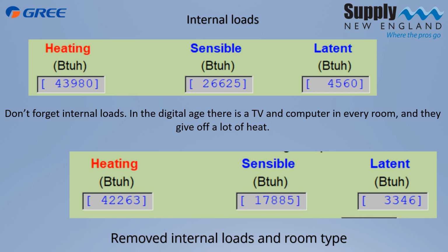By removing the internal loads, look what happened. We changed our heating BTUs. Not a lot, but some. Look what happened to our sensible though, guys. We took our sensible from 26,625 all the way down to 17,885. That's a huge difference, guys. So we've got to be careful with that. We affected our latent as well. We went from 4,560 down to 3,346. So make sure you're taking those internal loads into consideration.